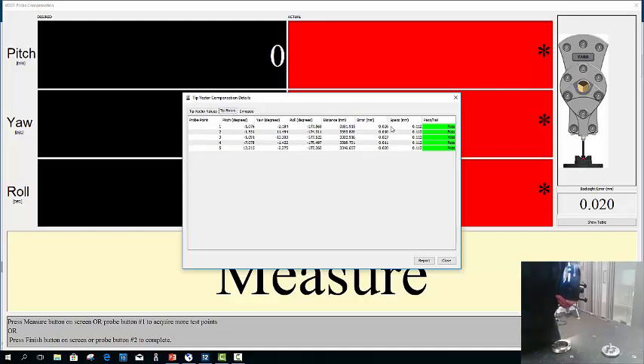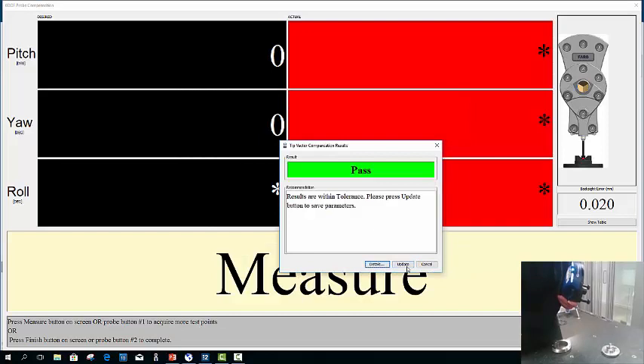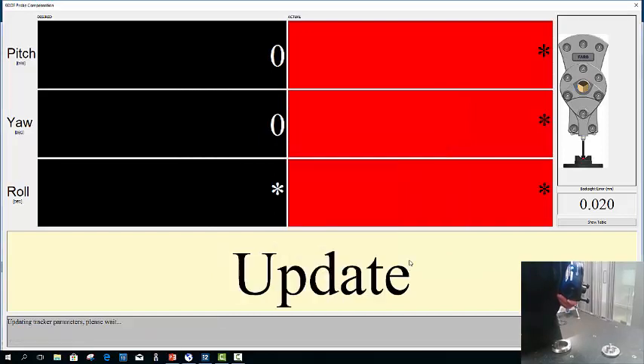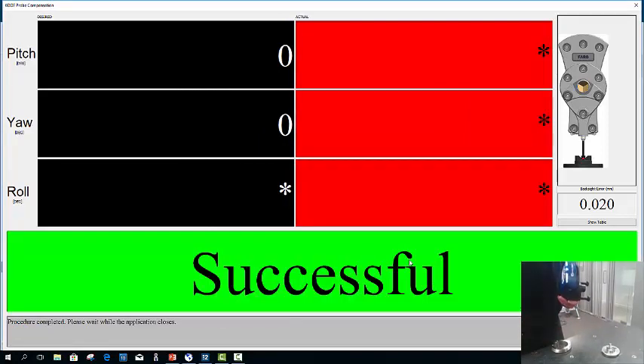The errors are the actual values, and the specification is the tolerance that you have to fall within. As you can see, you would expect the errors to be below 50% of the accuracy spec. You can report these if needed, but if not, we can just update the compensation results. And that is how you compensate the 6Probe.